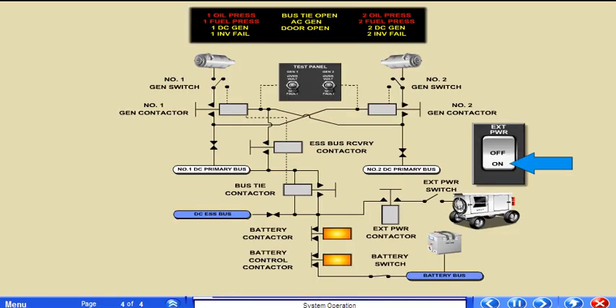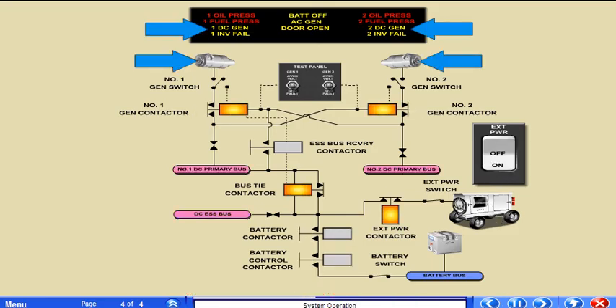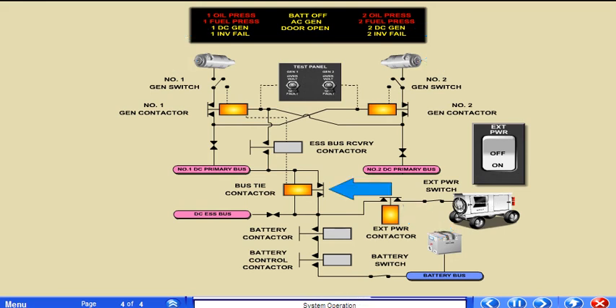When the external power switch is selected on, the generators must be offline, otherwise the external power contactor will not close. The bus tie closes automatically and the battery contactor opens. If a valid source of external power is connected, both primary buses and the essential bus are powered.